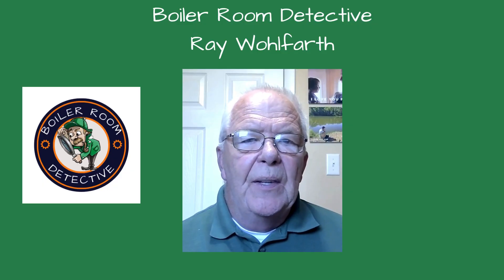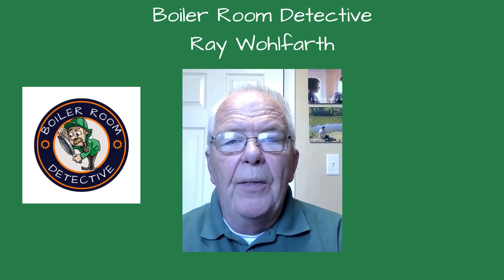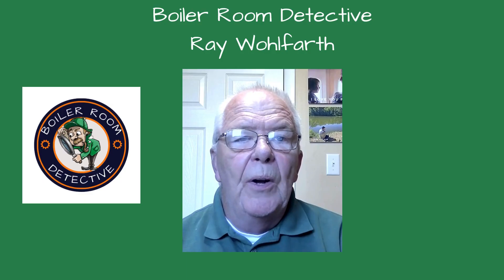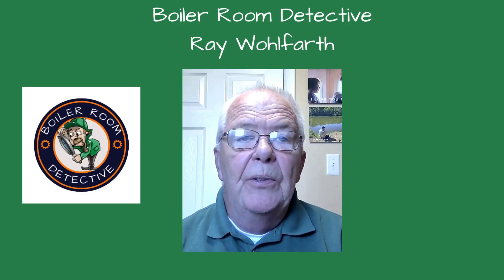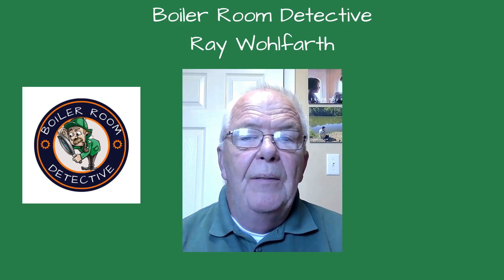Welcome, friends, to Understanding Steam Heating Boilers. I'm your boiler room detective, Ray Wohlfarth. When you're looking at steam systems, there are two types of boilers that you're going to see: fire tube and water tube. Fire tube boilers have the fire and hot flue gases inside the tubes and the water and steam surrounding the tubes. Water tubes have water and steam inside the tubes and fire and hot flue gases surrounding the tubes.